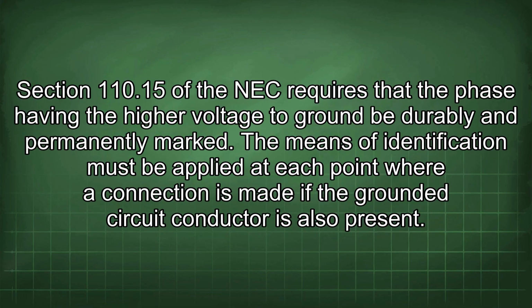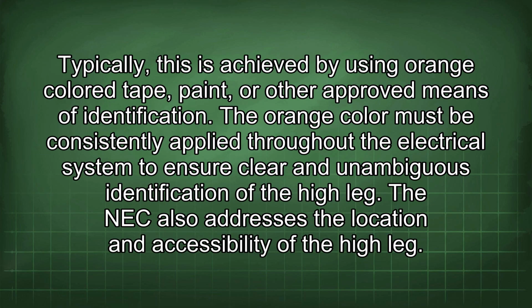Section 110.15 of the NEC requires that the phase having the higher voltage to ground be durably and permanently marked. The means of identification must be applied at each point where a connection is made if the grounded circuit conductor is also present. Typically, this is achieved by using orange color tape, paint, or other approved means of identification. The orange color must be consistently applied throughout the electrical system to ensure clear and unambiguous identification of the high leg.